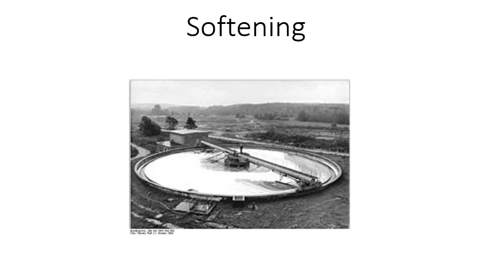If total alkalinity is greater than total hardness, then all the hardness is carbonate hardness, temporary. If the hardness number is higher than the alkalinity number, then non-carbonate hardness is present, permanent hardness, along with carbonate hardness, temporary. By subtracting the total alkalinity from the total hardness, the amount of each type of hardness can be determined. Permanent hardness equals total hardness minus alkalinity.